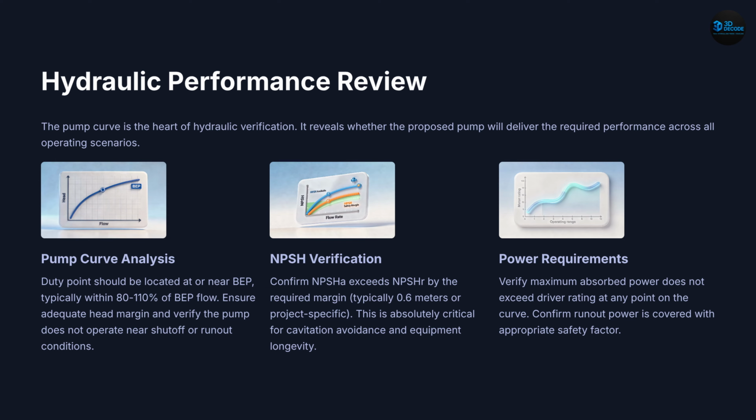Slide 8. Power check. Verify maximum power at runout condition. Ensure motor rating is sufficient. Ignoring this can lead to motor trips.